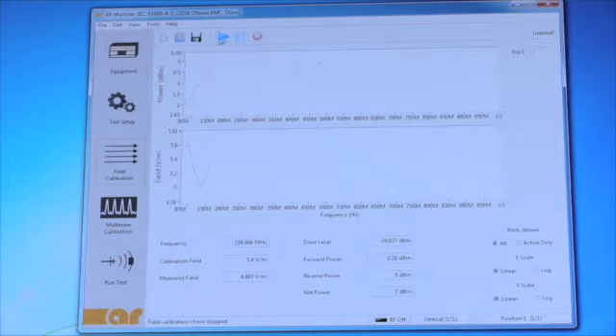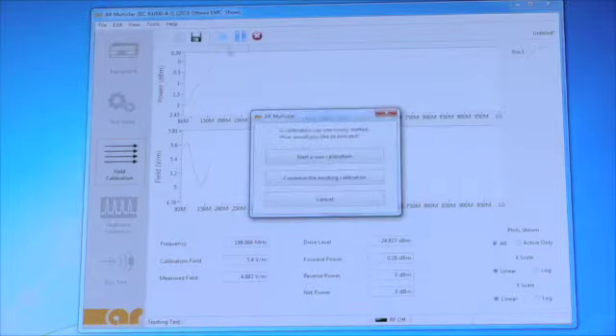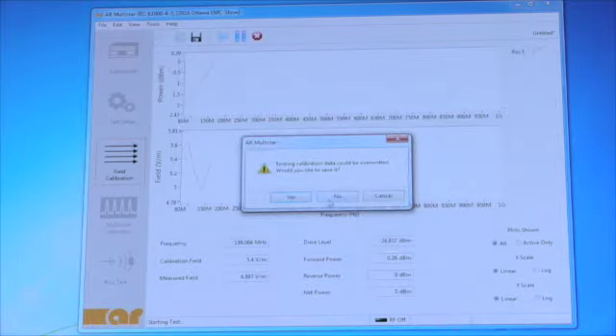So you come up here and hit the play button. I'm going to start a new calibration since I ran one. I'm not going to save the old one. Okay, here is where I can set my field level tolerance and my power level tolerance. I can set if I'm going to do constant field or constant power leveling on there. And I can drop the level between frequency steps. I think the MIL standard has you doing that.